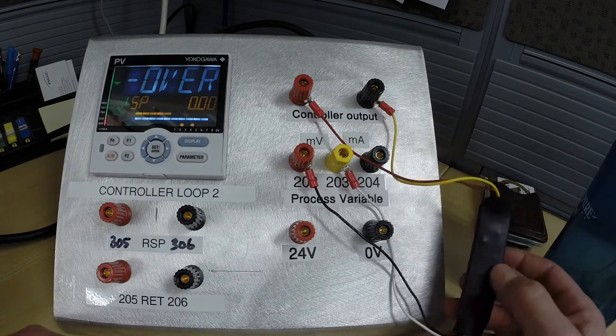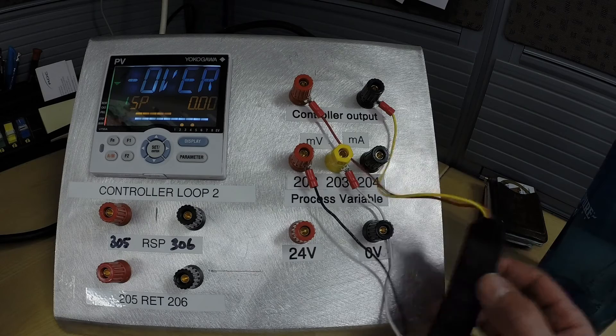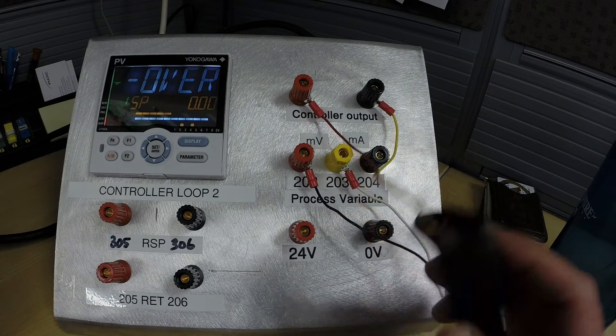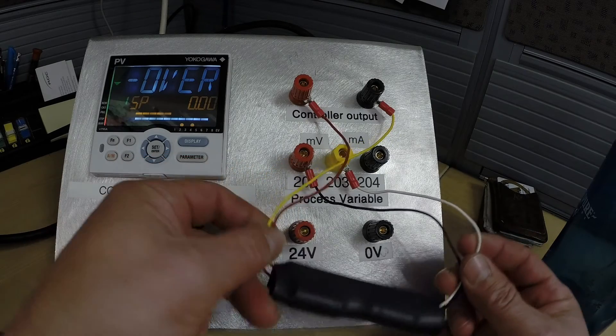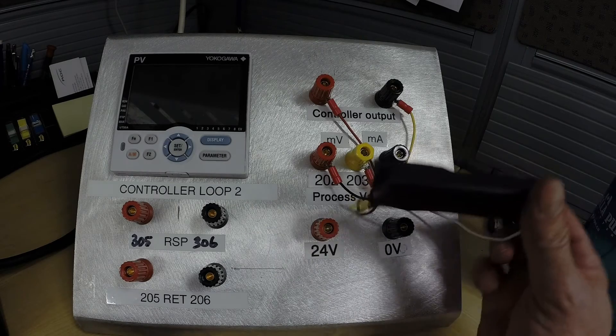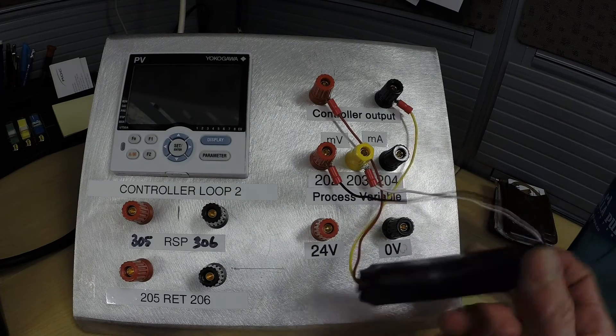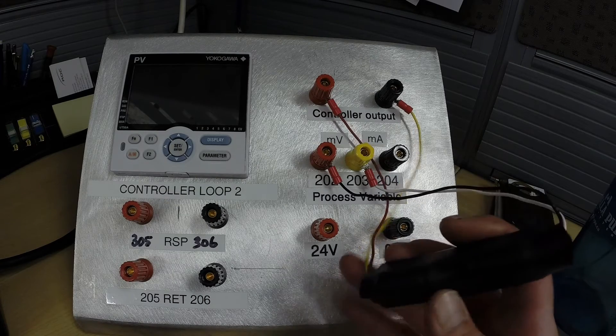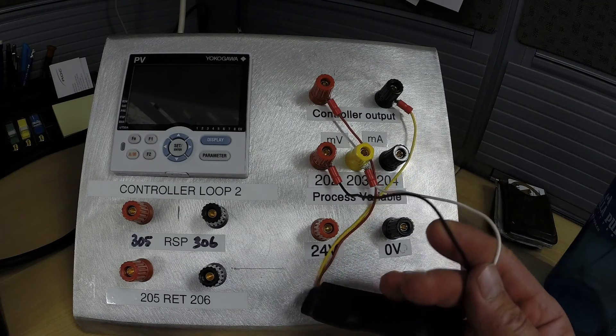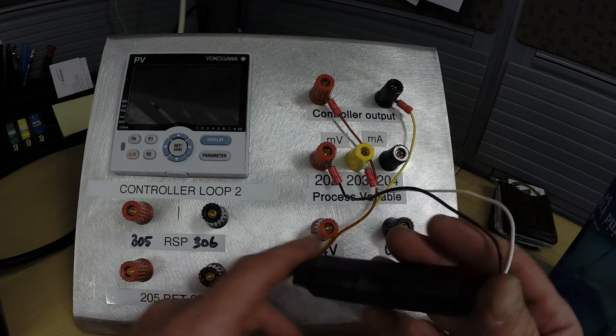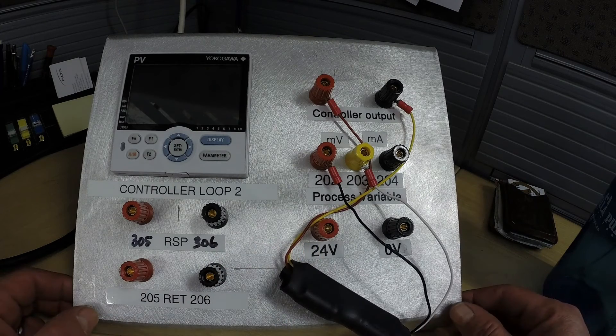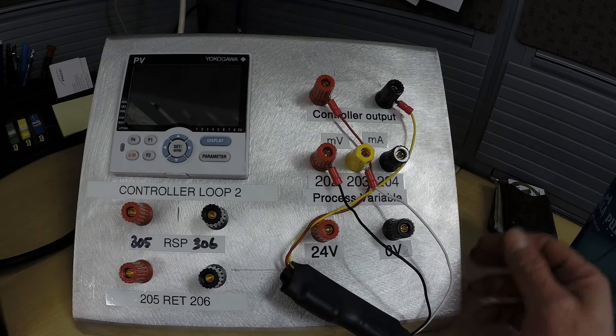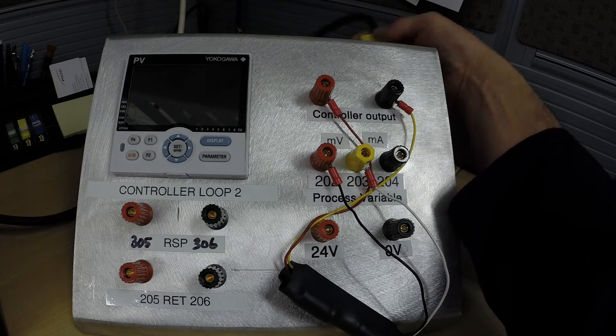We now have to walk through the parameter settings for temperature which will be slightly different than the basic milliamp in, milliamp out parameter settings. Here we have our temperature simulator wired into our controller panel with red and yellow wires on the controller output and our black and white wires from the thermocouple. From this point we're going to turn on our Yokogawa controller and see how our parameter configuration is set up.